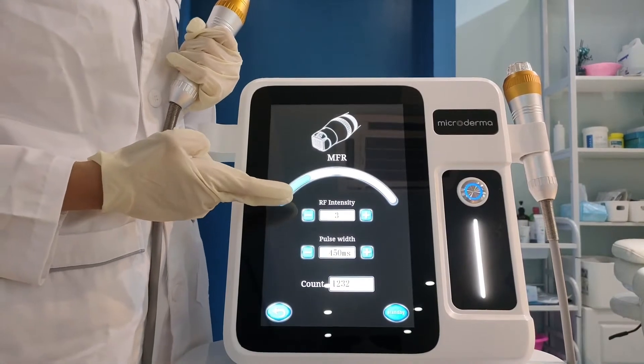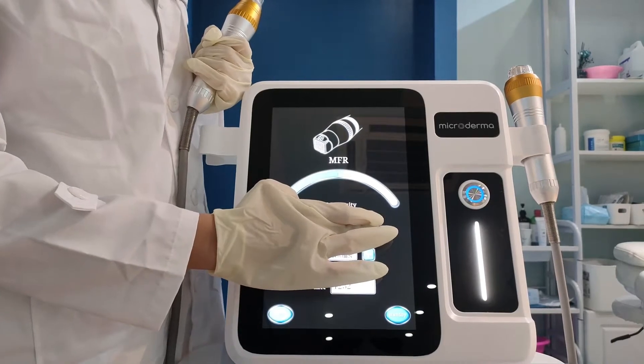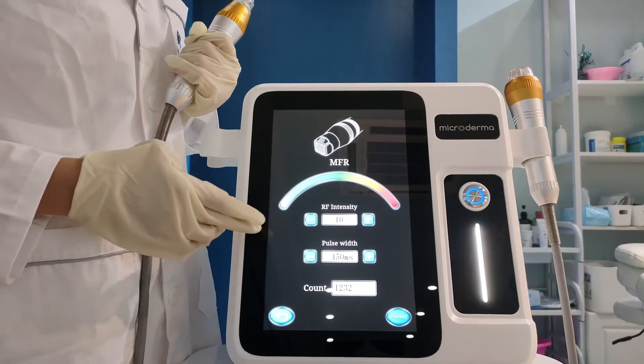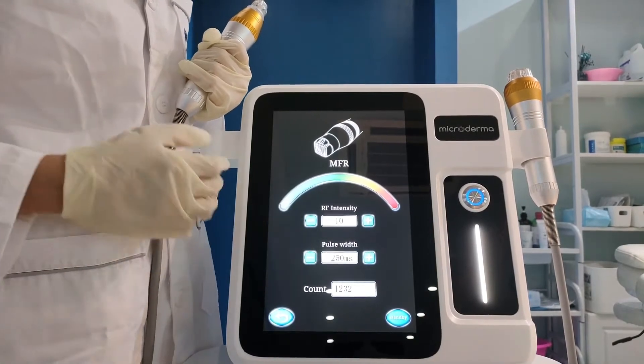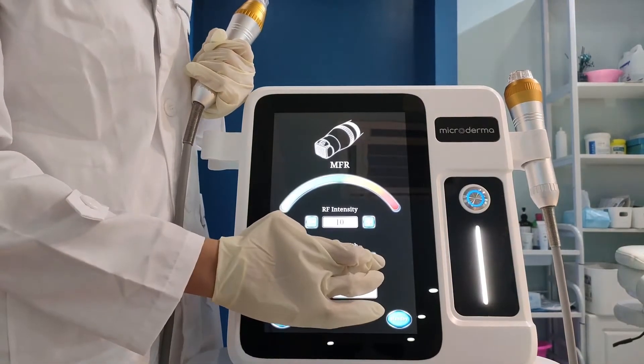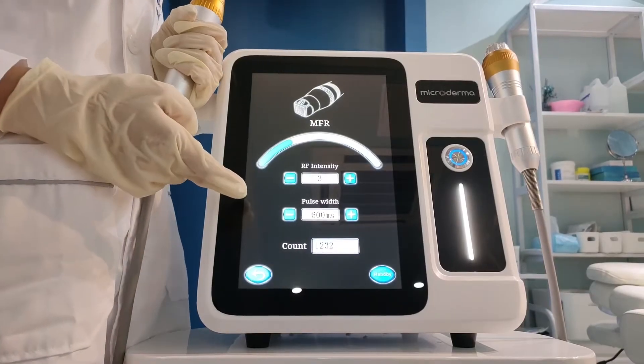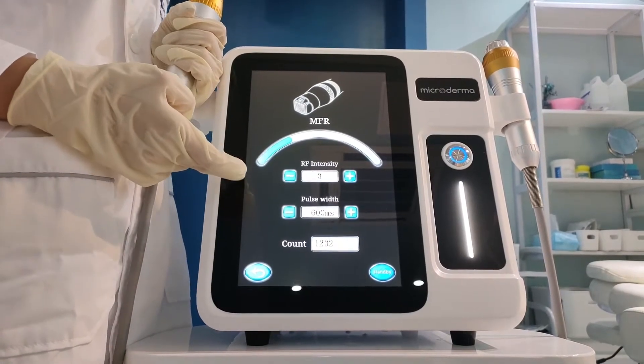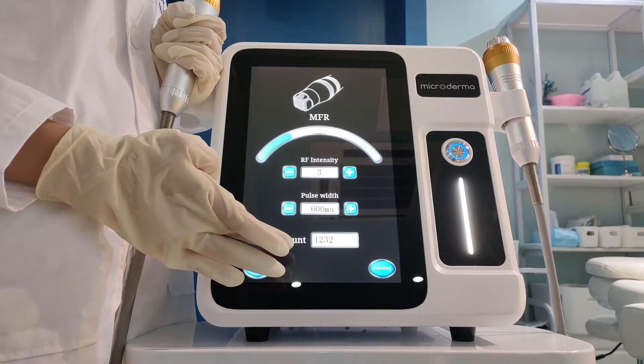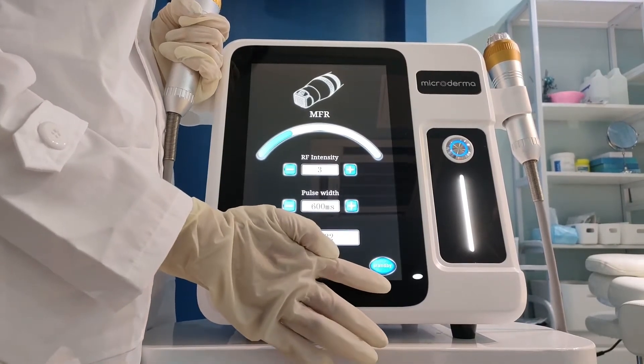This one is RF intensity. It has 1 to 10 levels. And this one is pulse width time. The range is from 250 milliseconds to 600 milliseconds — it means the time the needle works in the scan. This one is count, which means how many times the needle works. This button is standby; touch it to make the machine work.